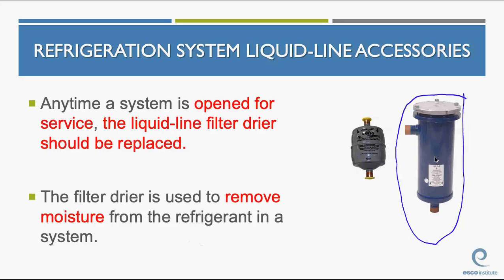You just evacuate the refrigerant out of this. You can't see it, but there's an access valve on the top of this. You valve this off, so there would be a valve there, there would be a valve there. You valve this off, you recover the refrigerant out of this, and then you can unbolt the top of it and pull the core out of it. Okay, this allows you to just change the core.